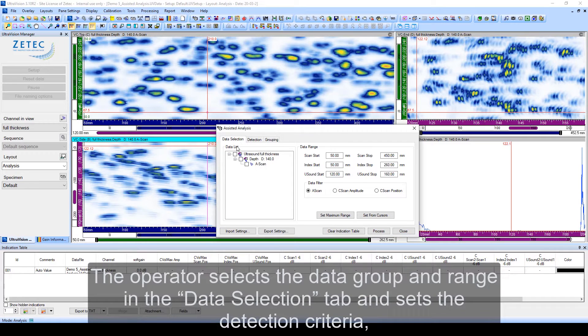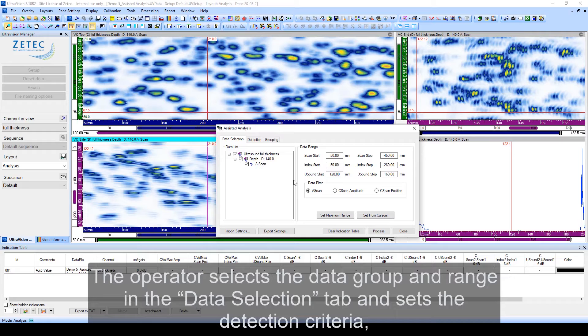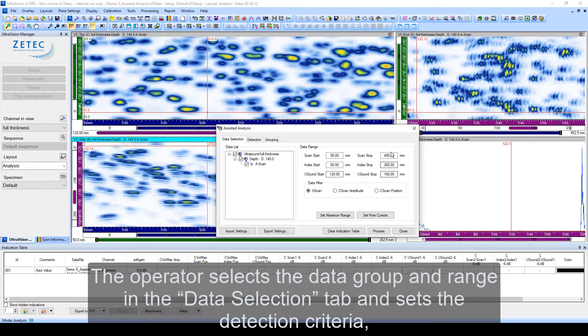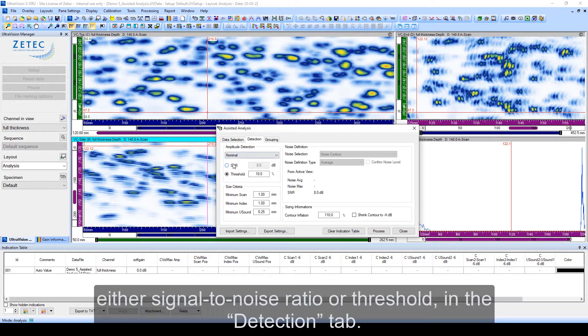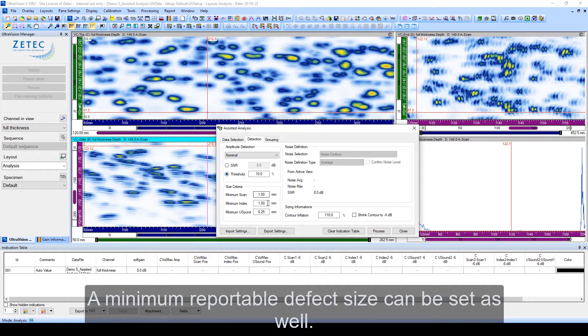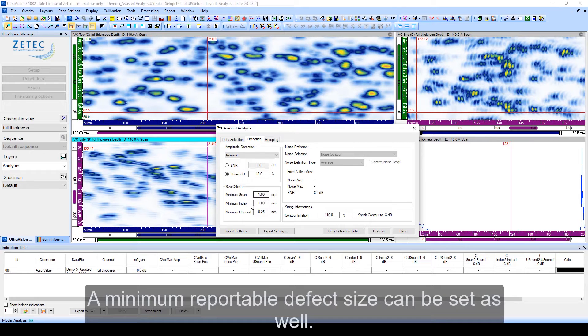The operator selects the data group and range in the data selection tab and sets the detection criteria, either signal to noise ratio or threshold, in the detection tab. A minimum reportable defect size can be set as well.